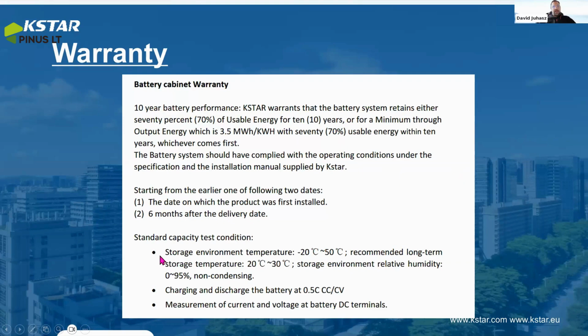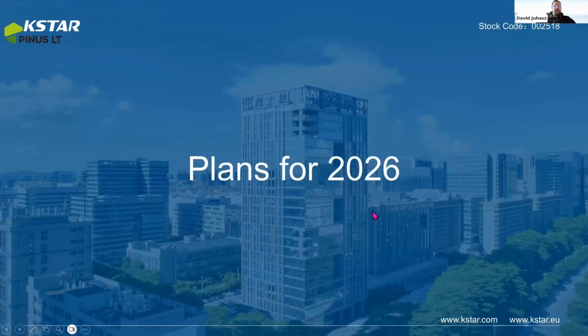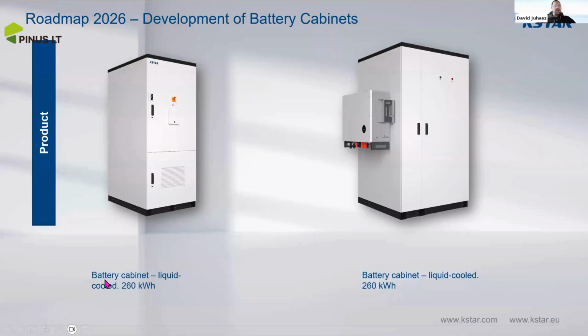Regarding storage, if we are storing equipment long term, we need to put it in an environment from -20 to 50. Okay, we have plans for 2026. We have the battery cabinet, liquid cooling, 260 kilowatt hour capacity, and these cabinets are liquid cooled.